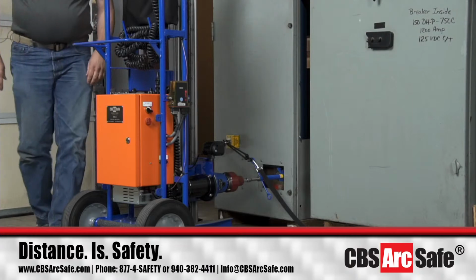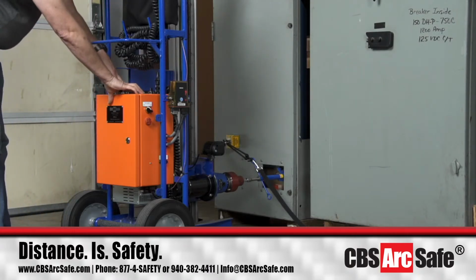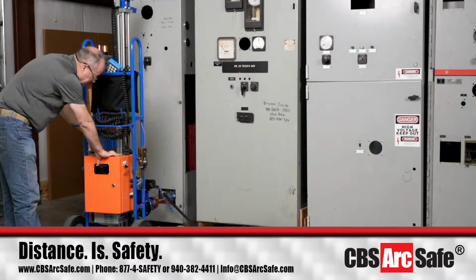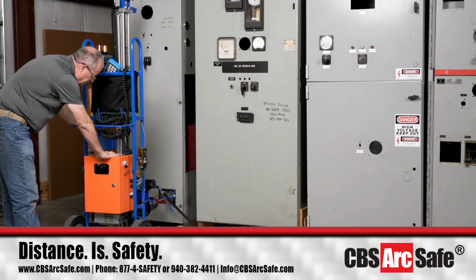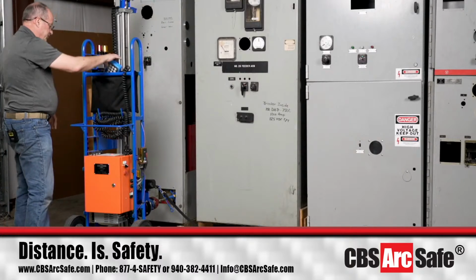Now, let's see, dealing with a vacuum breaker like this, my install should be about 14.5 or less, and my remove should be at about 12 or less. So right now we're fully removed, correct? We're in the remove position, that's correct.